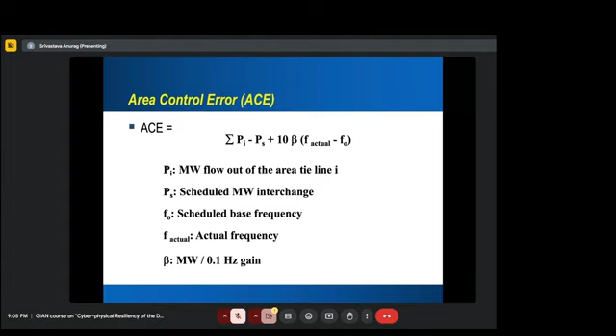This ACE, or area control error, is calculated that way and then implemented by controlling the power P, which we can increase or decrease only by controlling the fuel injection. That's what we do to maintain it.